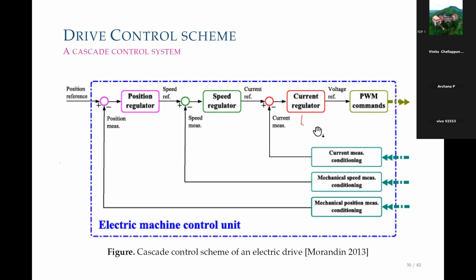If you look at the inner loop, it generates the PWM signals sent to the motor. This inner loop should be fast acting, generating signals faster than the outer loop. The speed regulator has a lower bandwidth compared to the current regulator, so the inner loop must be ready by the time the outer loop sends its signals. We need a higher bandwidth for the inner loop. This is one of the concerns we have to cater for during control system design.